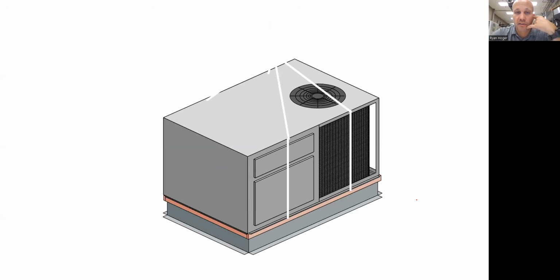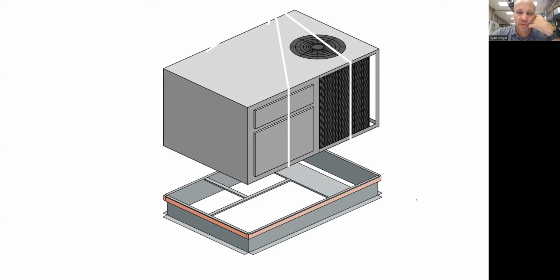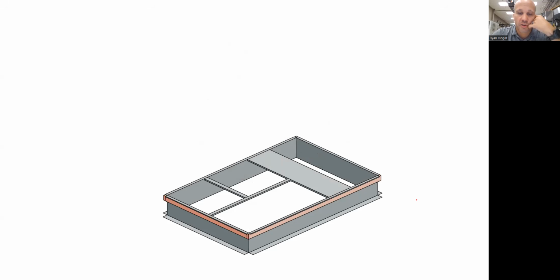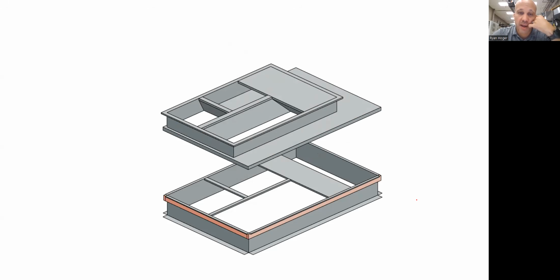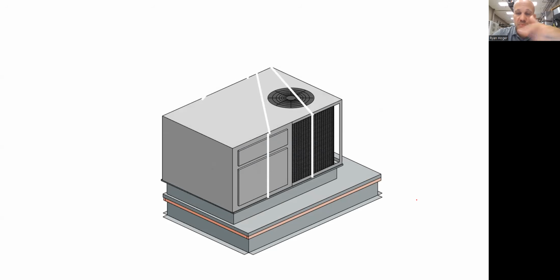This is a corny, cheesy little animation to kind of show what happens, but lift up the unit. There's the old curb and its duct connection points. Set this curb adapter on, and you can see the bottom is going to line up with the old curb. The top's going to line up with the new unit, and then set the new unit on it. In this particular example, we were going from a certain size unit, maybe a 10-ton unit, down to an 8-ton unit or something like that. That's why it's a little physically smaller. Usually they're not getting smaller, but sometimes they do.